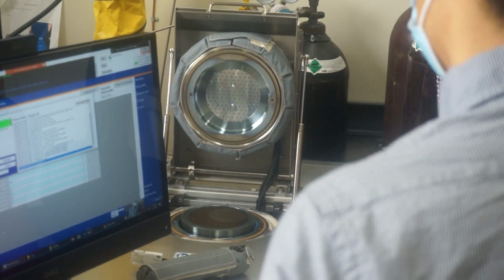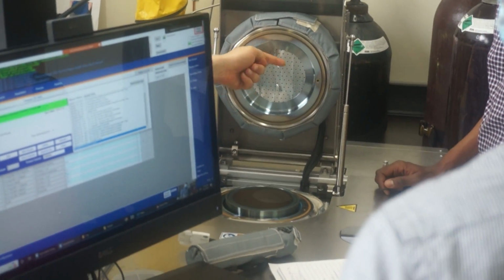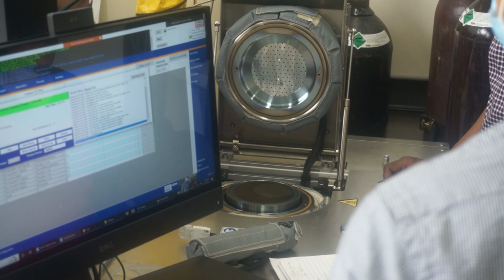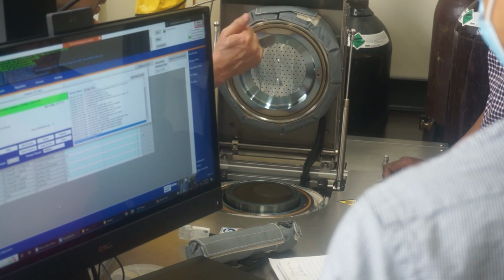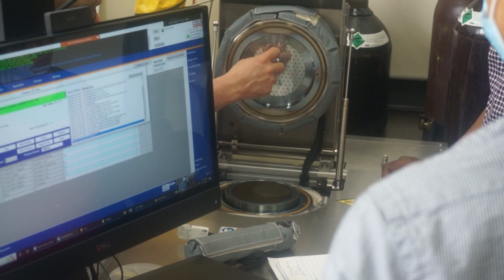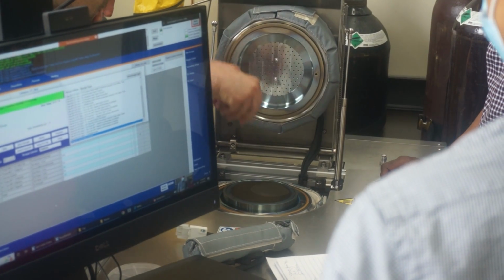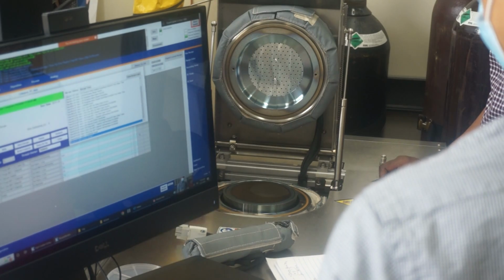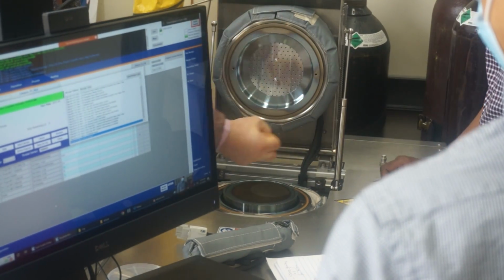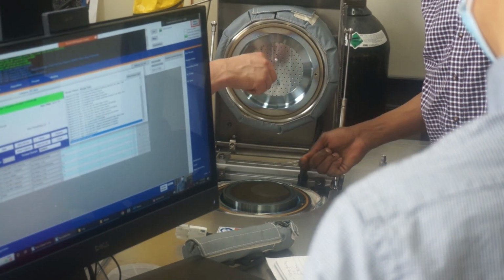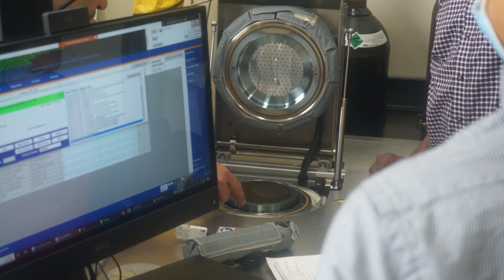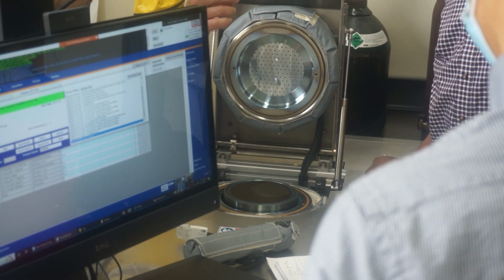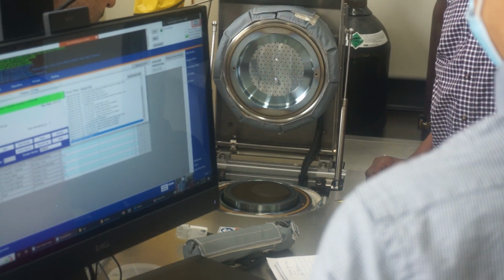So again, the condition materials coming from the TMA comes out of this hole into that hole, and then there's a passage that brings it out of the air shower. So it drops down and then it disperses, coming out from the TMA, going here and here. What are these two holes? These two holes is the purge gas from the argon that you see on the top of the vacuum screen, the one that changed to 600.